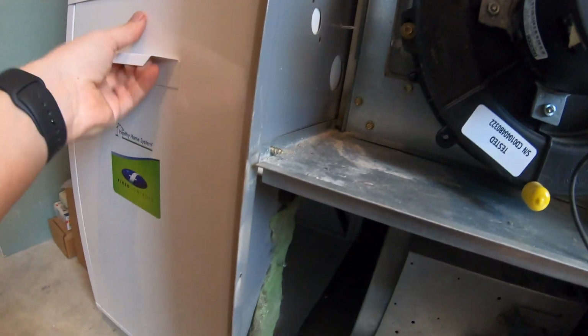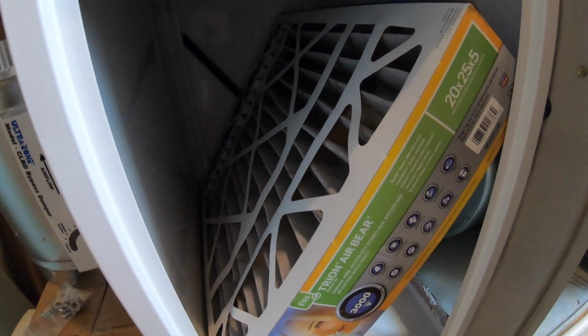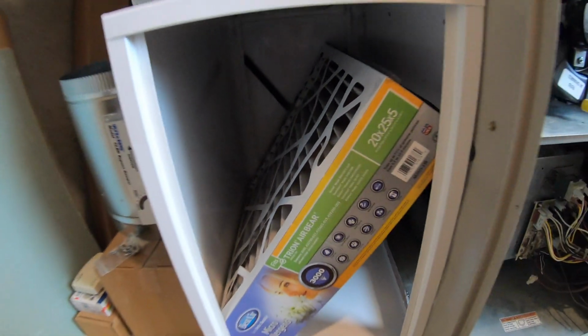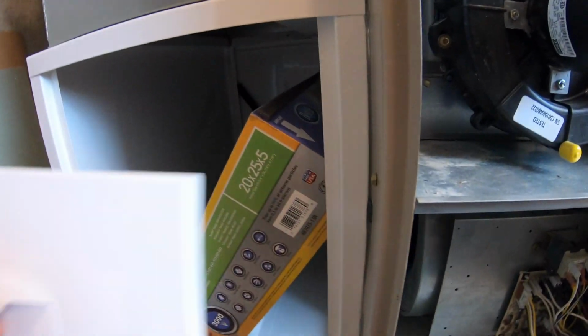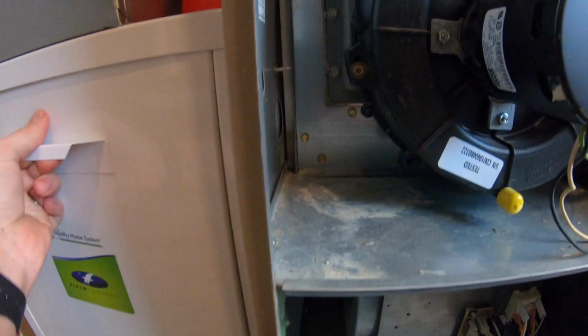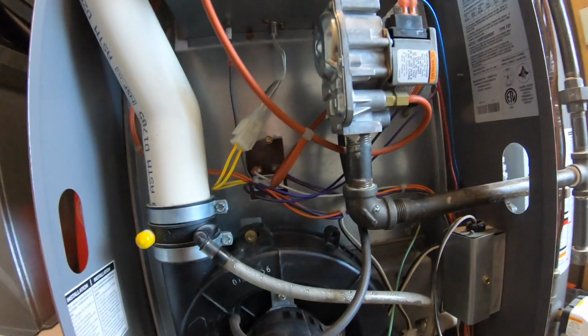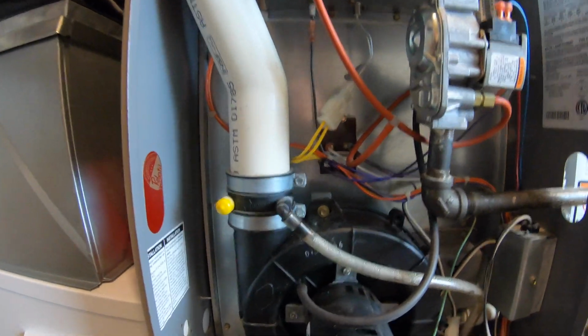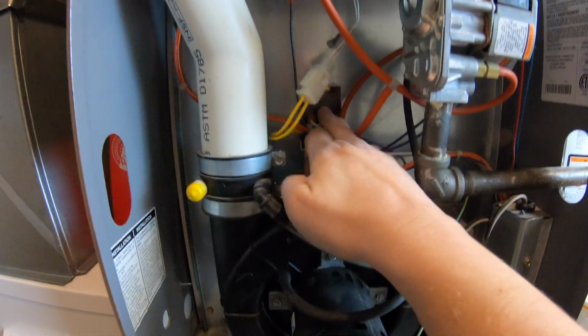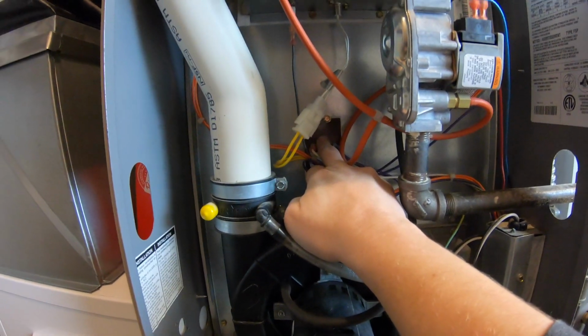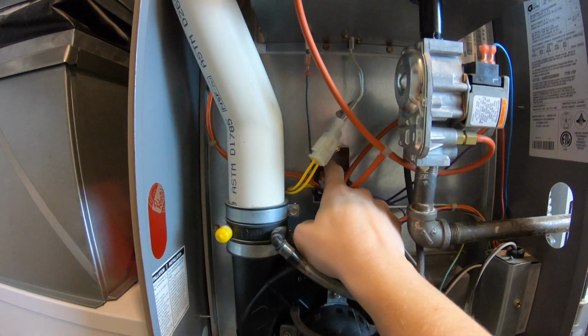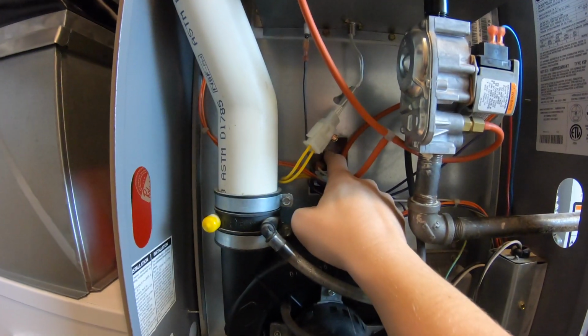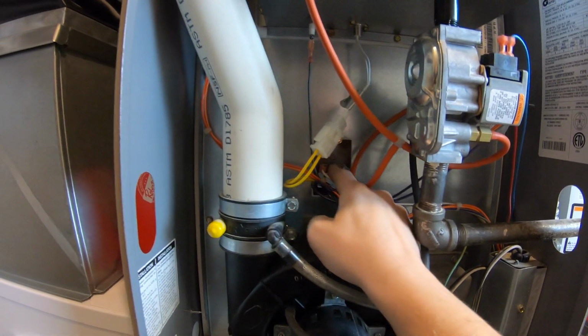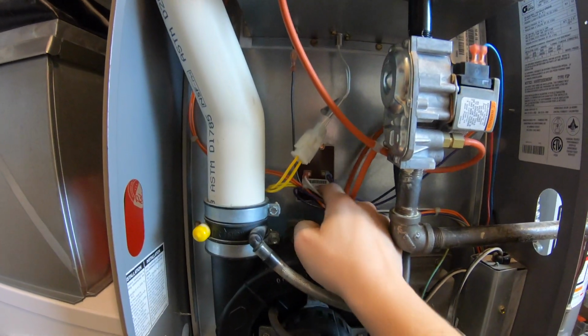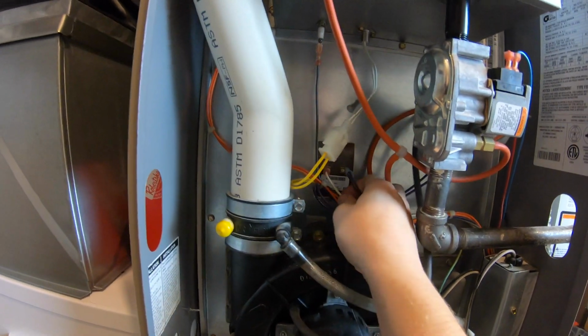We need to make sure that your filter is clean. Mine, for instance, is starting to get a little bit dirty. That filter needs to be cleaned to make sure you've got enough airflow across that heat exchanger to keep it cool. There are a couple safety devices in here to make sure that takes place. This guy right here is called the high temperature limit. That will monitor the temperature. Well, it really just is a little snap disc in there that if it gets too hot, will break this circuit right here, these two wires.